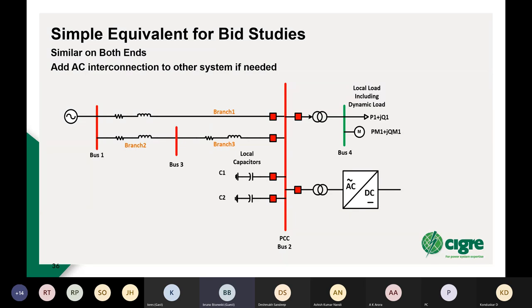So what would a simple equivalent for bid studies look like? It usually, as we said, has about three buses, and if you need the connection to the other side, it'd be the same or similar at each end, adapted from the AC system short circuit levels. And if you have a dynamic equivalent, also the inertias of the generators on each side, you might have a typical governor and exciter response in your machine. The three buses allow you to simulate converter station faults, remote faults at, for instance, bus three in this case, and you can model local capacitors and filters for dynamic voltages. You can model the DC in detail.